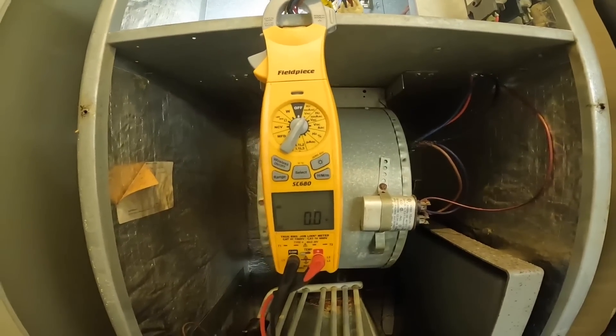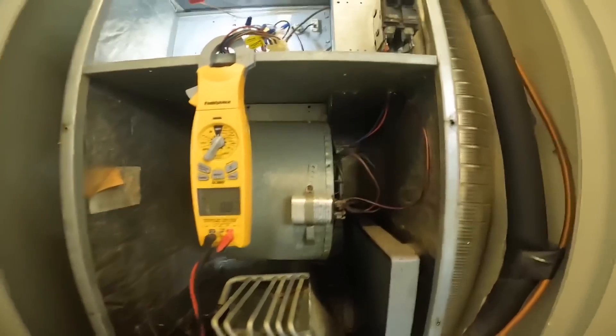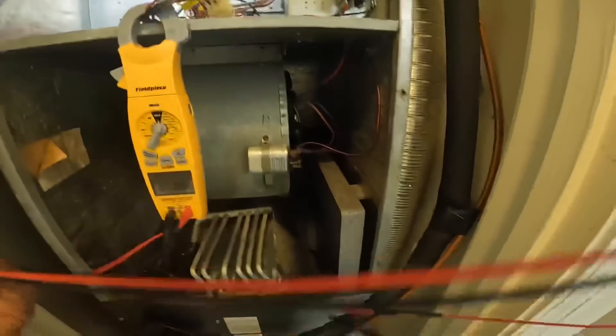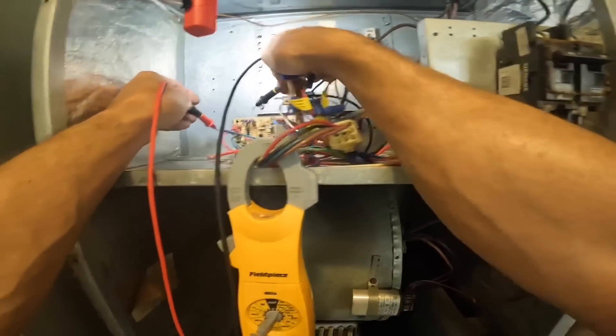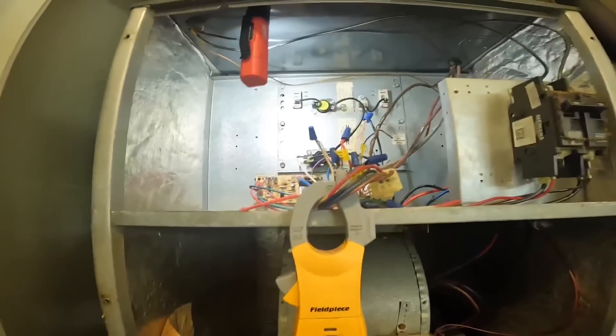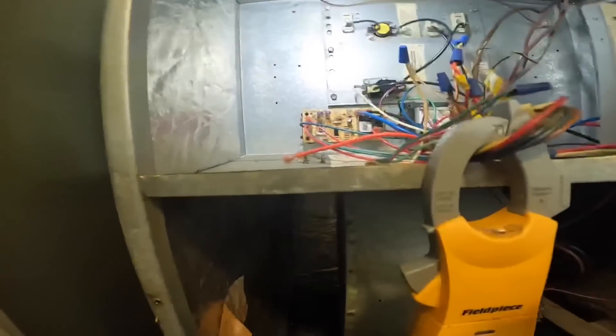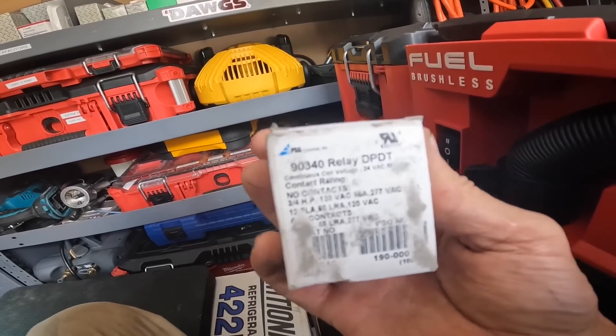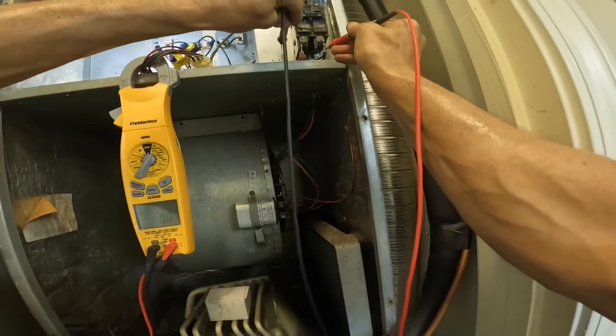That's my 24-7 hot. Let's make sure we're getting a call. And that right there — alright, so we're getting a call, but the blower is not coming on. We're going to replace that with a relay. We're going to use a 90340. First we need to confirm we have no power.